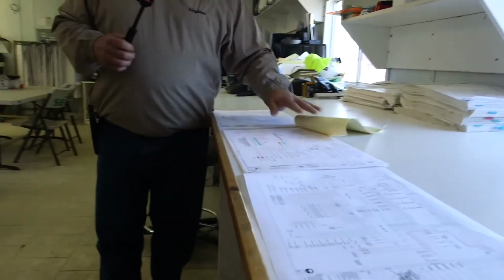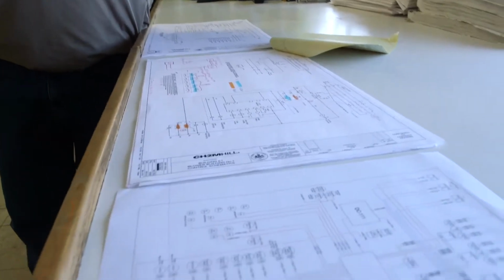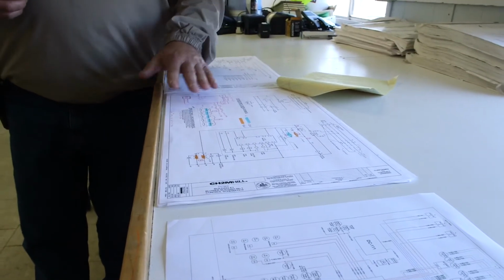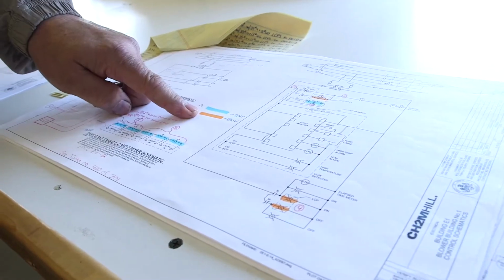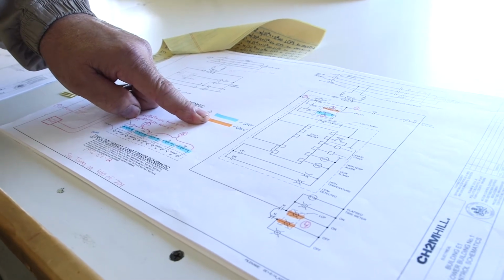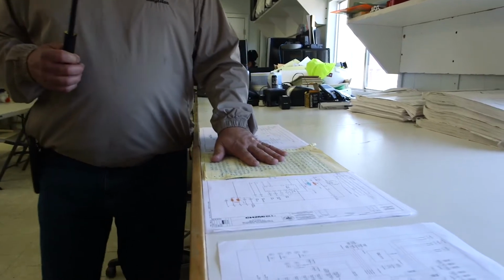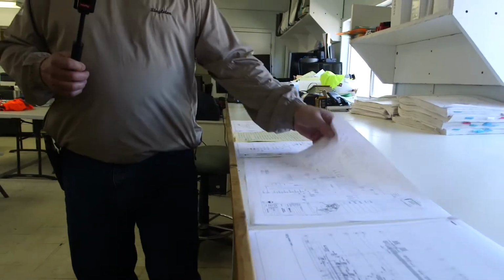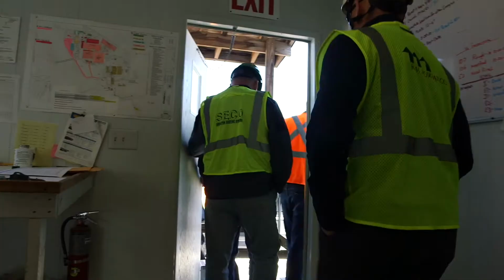You had 24-volt digital inputs, 120-volt digital outputs, 4 to 20 analog circuits. All the different systems, we had to pick apart, build our own conduit and wire schedules, and create a block diagram for each of the buildings we worked in. So a whole lot of work had to happen before we could start out in the field installing anything.